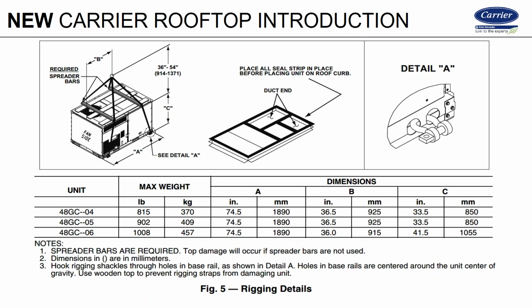So Steve, actually, it's more of a comment, I guess, than a question. Maybe it's a question. On a recent unit he installed, there's a spacer on the curb to push it tight to the airflow side. I assume he's asking if that's normal or if you see that often. There could be a spacer that you would insert over here, so you would hold it tight, but that would be like an HJ frame size unit. The HJs, I believe, have that little spacer plate, if that's what he's talking about. Could be. But bottom line, all units need to be tight back here on the air side.